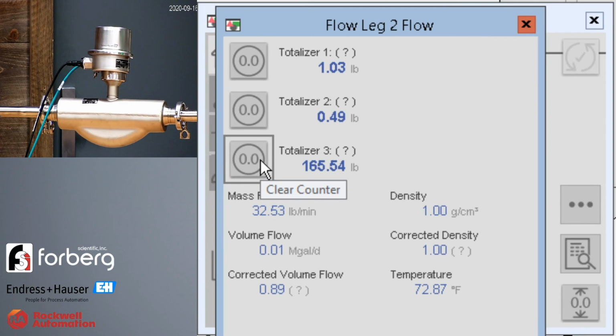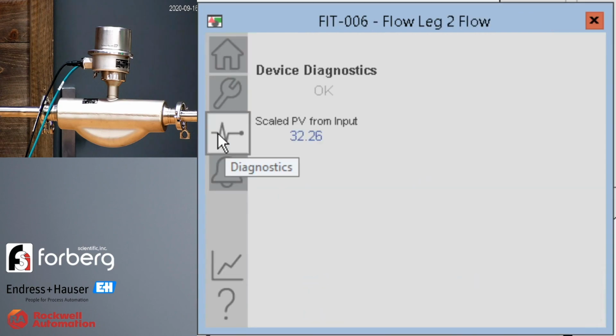Along with all these process variables that are available, you also get a diagnostics tab very similar to what we got on the other Ethernet IP devices and the HART devices, where you get a fault number along with the human readable words that correspond to it, because that particular device has a specific diagnostics file for that exact device.